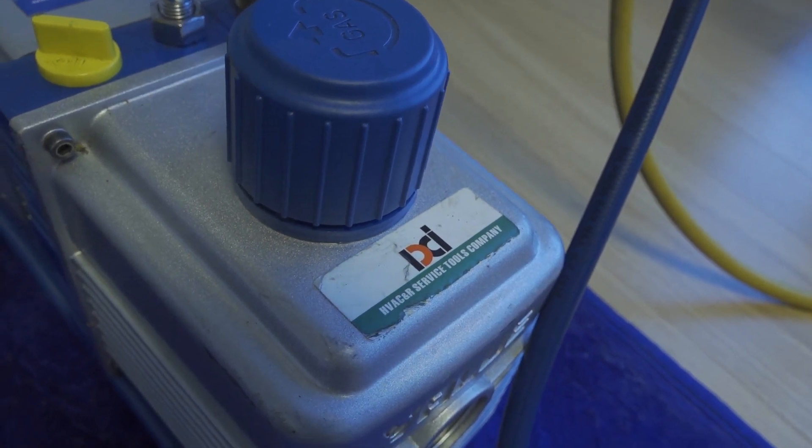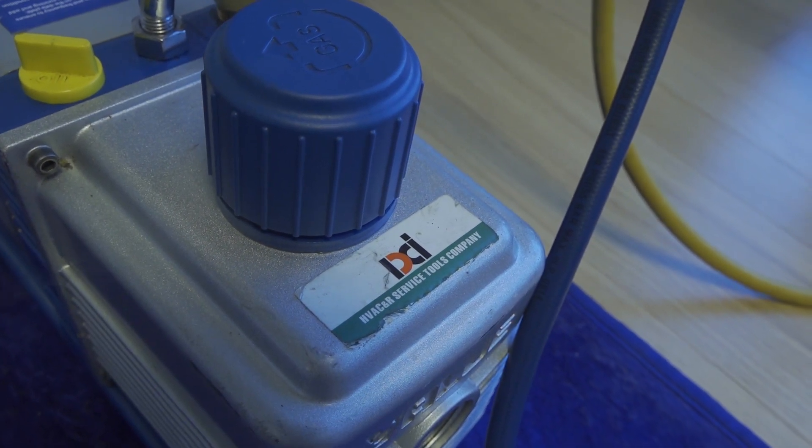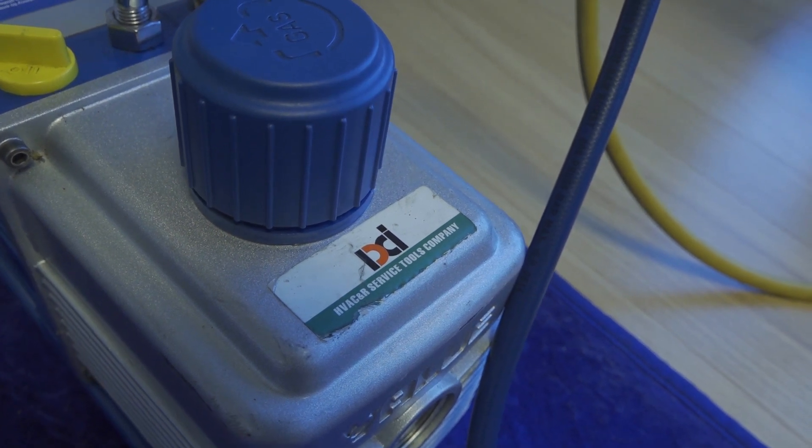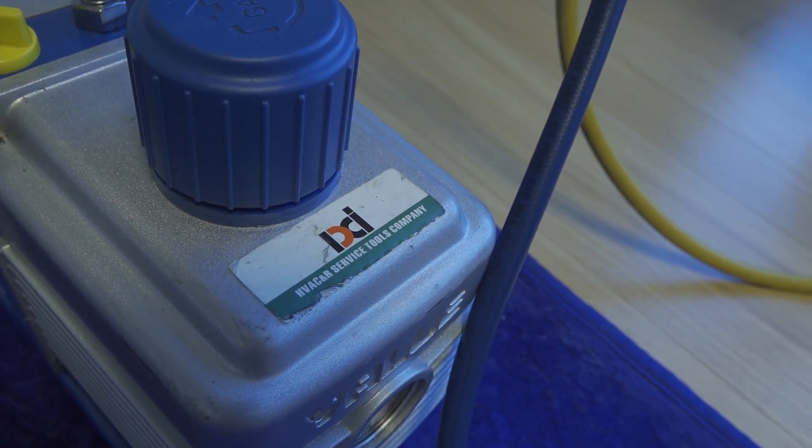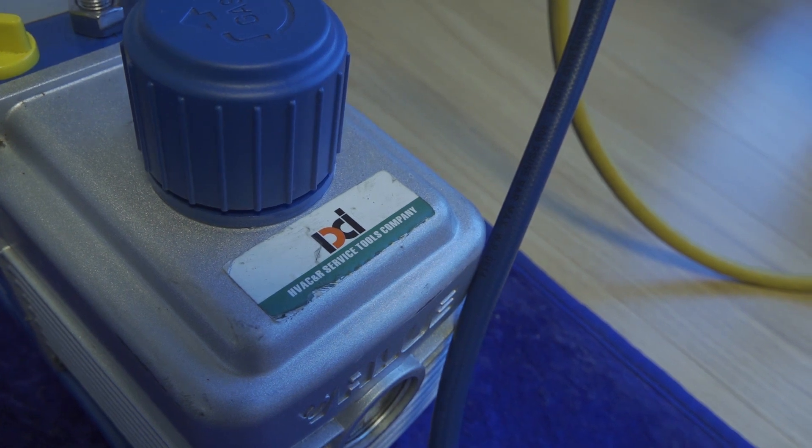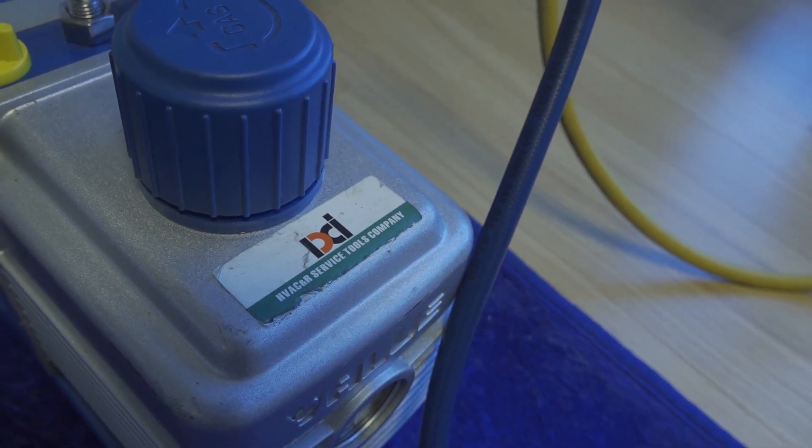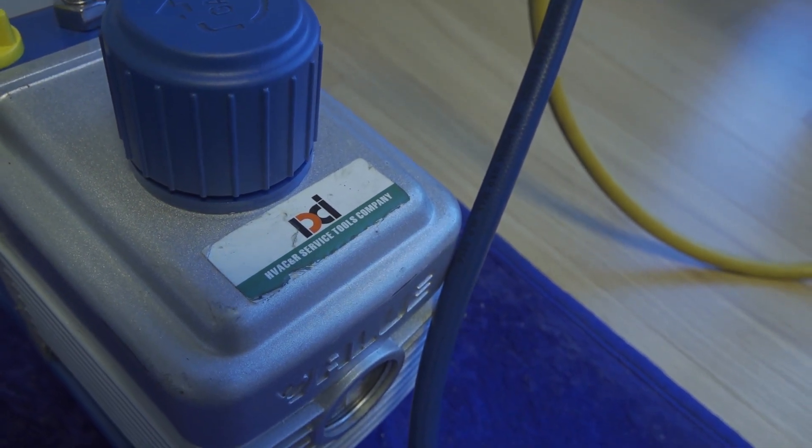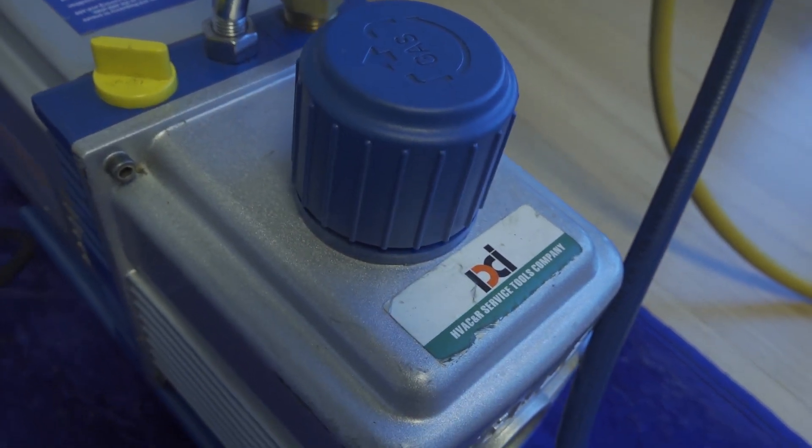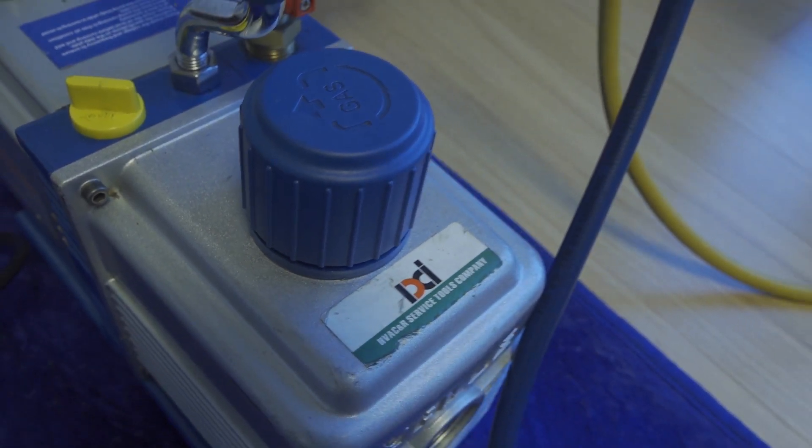Usually when you start pulling vacuum, this disappears within 2 to 3 minutes. If you continue seeing this smoke, you should suspect there might be a leak somewhere. So please watch for this when pulling vacuum.